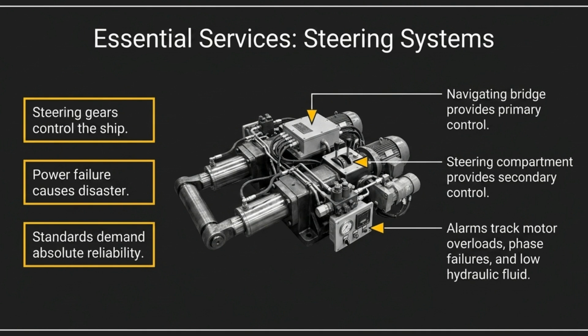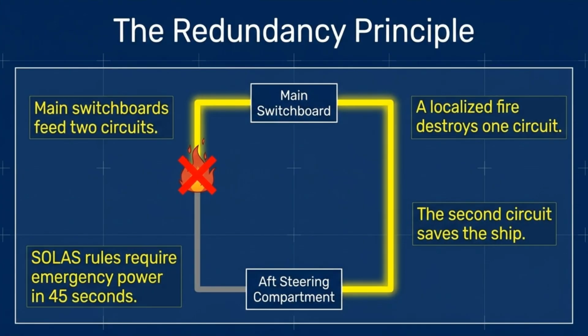Steering systems are critical services. Standards demand absolute reliability for these systems, with primary and secondary controls, along with comprehensive alarms to prevent potential disaster. Redundancy is a core principle. By using separate circuits, a fire in one area won't disable the entire ship. SOLAS regulations even mandate emergency power restoration in just 45 seconds.